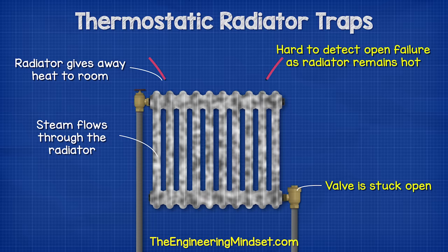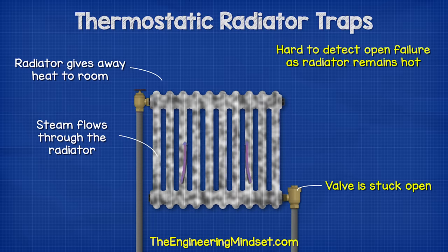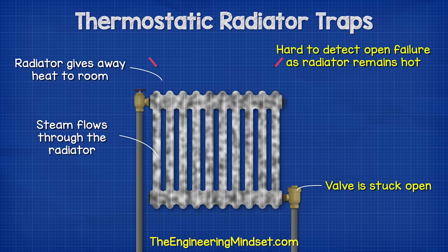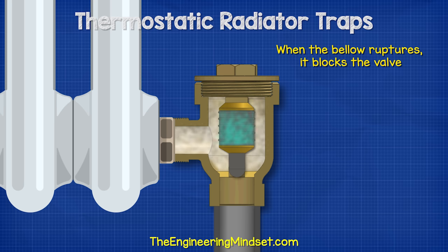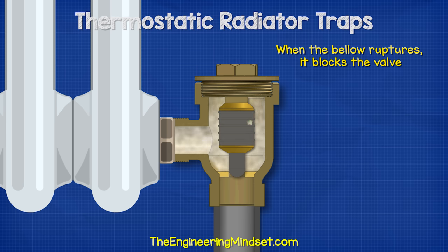An open failure can be very hard to detect because steam is still flowing through, so the radiator will still be hot. The other type of failure is a closed failure. When the bellow ruptures, it drops and blocks the valve, effectively closing it. During normal construction, the bellow hangs freely and blocks the outlet; water is placed inside and a vacuum is formed to draw out the air, causing the bellow to rise up and compress. If the bellow ruptures it drops and blocks the outlet, the radiator will eventually stop giving out heat, and you can tell the valve has failed.